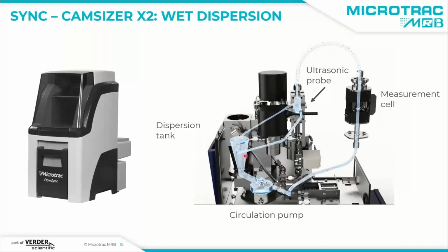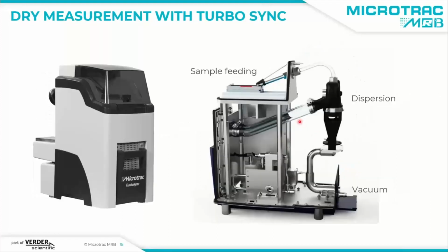And this is where you would put your sample. This is where you introduce your particles to the system. There's also an ultrasonic probe. The ultrasonic probe can disperse the particles and help separate particles from each other in case they are sticking together.